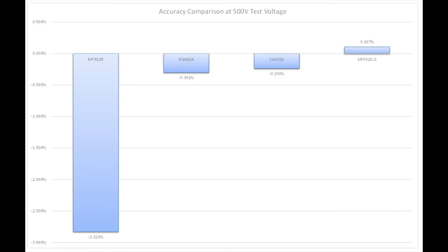Okay this is the overall accuracy at the 500 volt test voltage. You can see the MTR105 minus 2.8%, minus 0.3% for the 1461A, Chauvin Arnoux is minus 0.236 and the MIT 420 is 0.107, so it's actually the most accurate of all the units across the 500 volt test voltage.